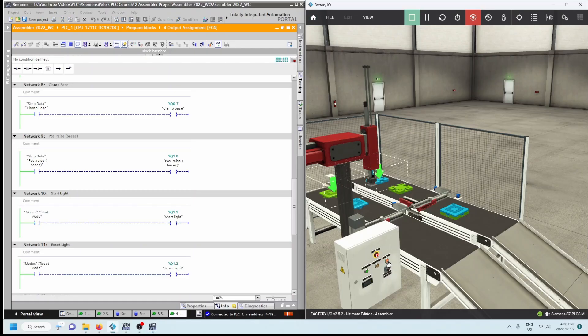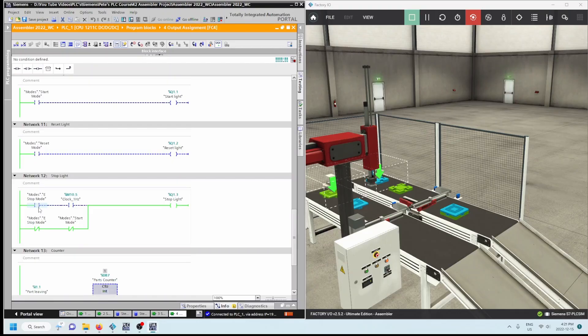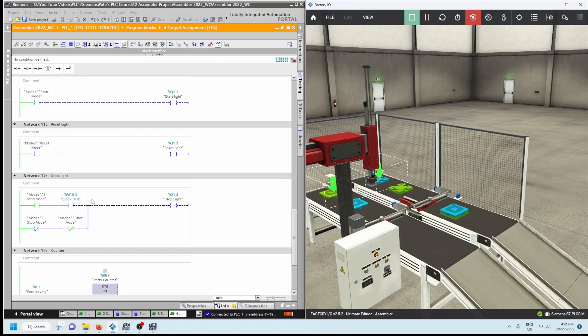We go to Q0.7, then Q1.0 for positive raised basis. If I press stop, start mode turns off. Start mode turns on Q1.1 for my start light. Reset mode turns on reset light Q1.2. The stop light has two portions: if I'm not in e-stop mode and not in start mode, there's a solid red light on the stop push button. If I press e-stop, I'm in e-stop mode — the clock memory byte, specifically %M10.5, flashes at one hertz, making the stop push button flash. Releasing e-stop: no longer in e-stop mode but still not in start mode, so stop light is solid red again.